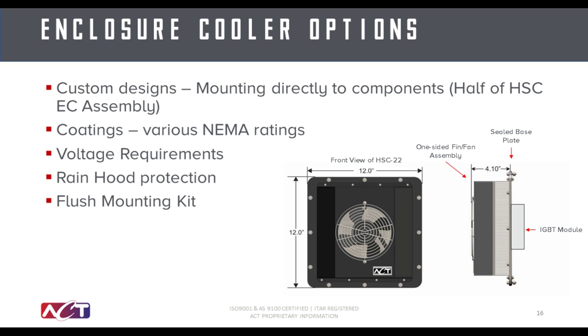One example itself is mounting your modules directly to a portion of that HSC or HPC model for limited volumetric parameter applications. In this example, we have an HSC 22 model to a customer that mounted their IGBT module directly to the base plate itself. This base plate, again, still comprises the sealed wall of the enclosure, but provides a direct route of heat transfer to cool that module.